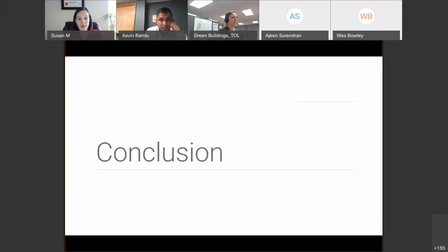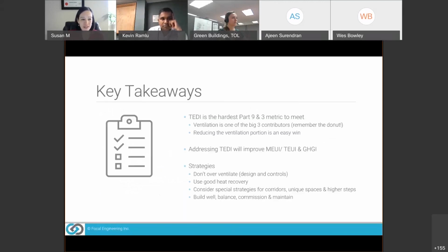Okay, so just wrapping up here, the key messages we really wanted to leave everyone with is that TEDI is going to be, generally speaking, the hardest Part 9 and Part 3 metric to meet. And ventilation is one of those big 3 contributors. So remember the donut. Reducing ventilation is generally an easy win. And when we say easy, we also mean cost effective. Keep in mind too that addressing the TEDI will usually improve the MEUI, TEUI, and GHGI, and usually get you to the requirement you need to hit.